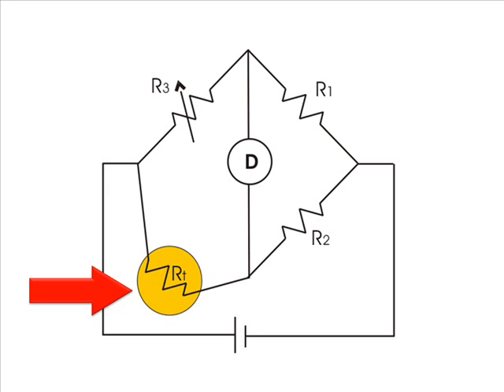But main disadvantage of this arrangement is it's not free from contact resistance of the variable resistance. As this contact resistance directly comes under the bridge circuit, it affects the reading of the temperature and introduces error in reading.